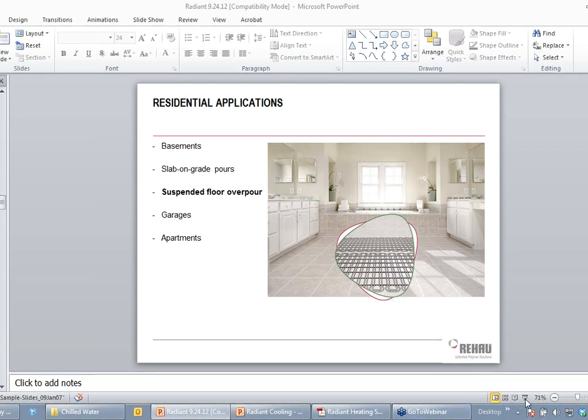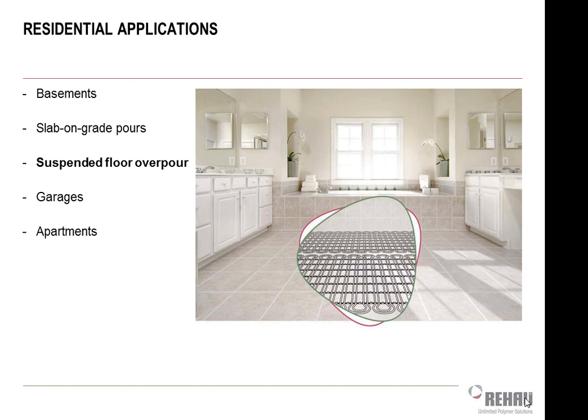All right, so let's look for a little bit at some typical applications that you might be using these type of systems on. Like I said, in residential spaces, either as a retrofit or a newer install on the upper floors, you can put the tubing underneath the tile. You can staple it up if it's a first floor from the basement. If it's a second story, you're obviously going to have to pull the floor up. But you can do that underneath the tile. You can also embed it right in the concrete, which is one of the more comfortable ways to do it. It's very easy to do for basements and slab on grade type applications.